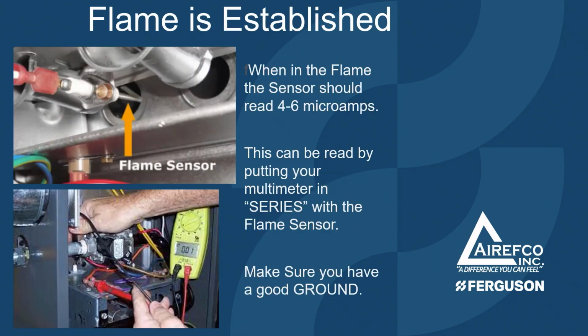After the gas valve has opened, there should be ignition on the burners. The flame is then established via the flame sensor. When in the flame, the sensor should read between 4 to 6 microamps. This can be read by putting your multimeter in series with the flame sensor. Also, make sure you have a good ground on the furnace, as a good ground is necessary for the proper operation of the flame sensor.